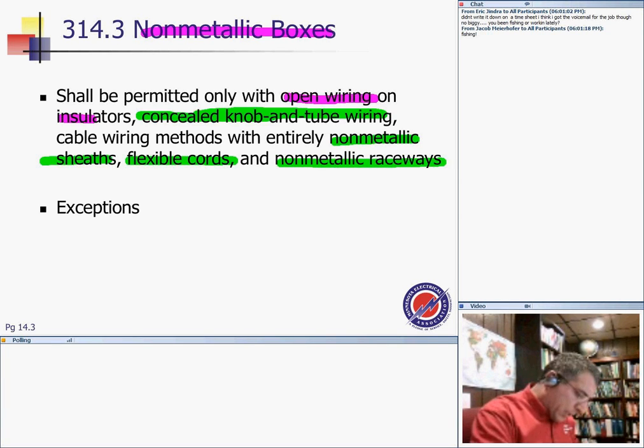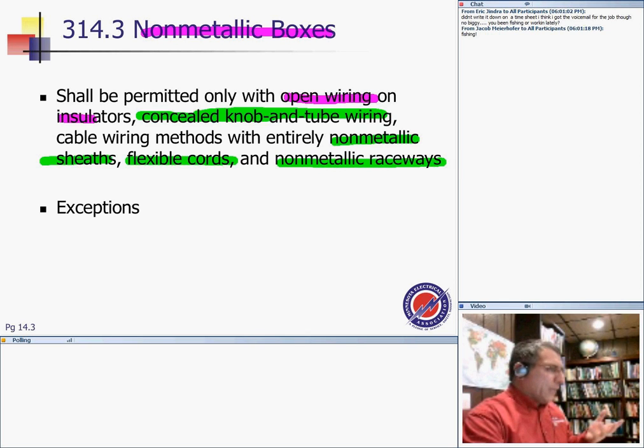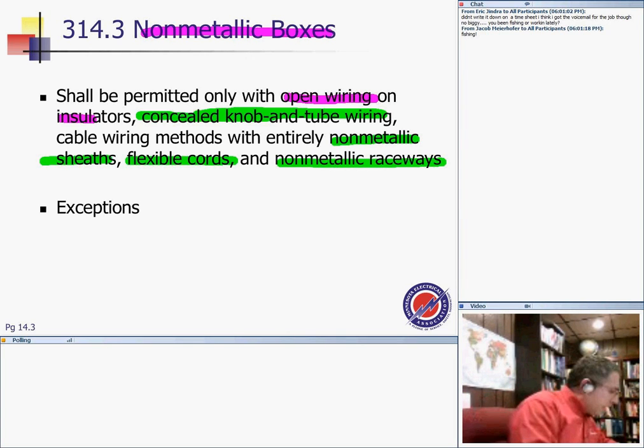If you look at exception number 1, it says where internal bonding means are provided between all entries, non-metallic boxes shall be permitted to be used with metal raceways or metal armor cable. Where a means of bonding is provided, because you can't bond to the device, you have to provide a means of bonding. Then you can use MC cable. Where bonding means with the provision for attaching an equipment bonding jumper inside the box are provided between all threaded entries in nonmetallic boxes listed for the purpose, nonmetallic boxes shall be permitted to be used with metal raceways or metal armor cable.